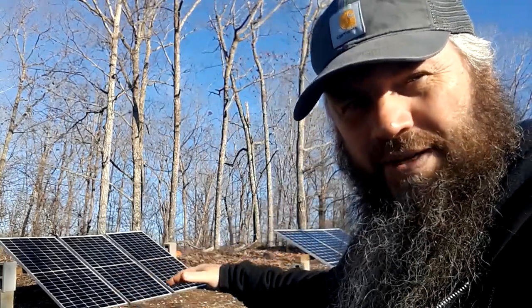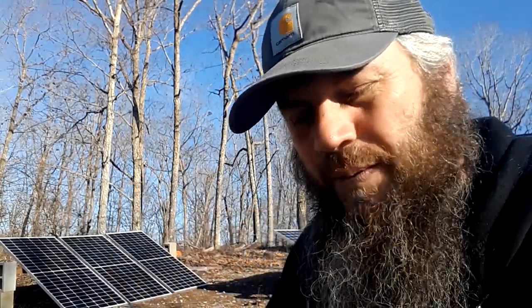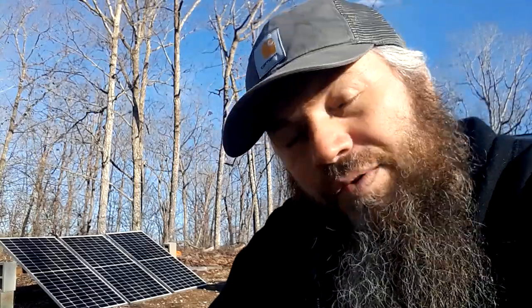It is not ideal for us to hook 4 panels up in series. What'll happen in the winter is we'll exceed that 150 VOC inside that charge controller. It'll go into a fault error mode, it'll go into protection mode, it'll shut down, and we can't have that. And the sound inside the house is pretty annoying.